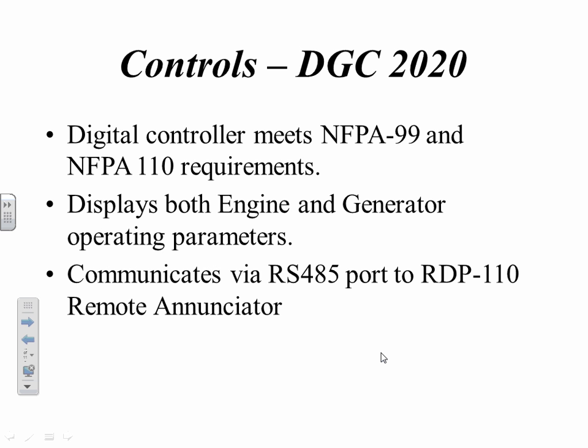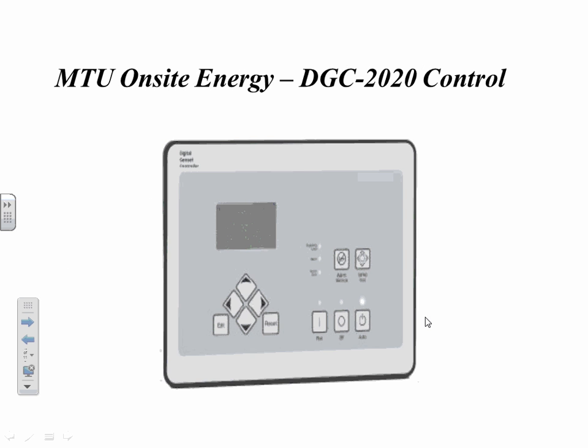Control options that we have. NFPA 110 is probably a regulation you may or may not have heard of, and that applies to generator sets. It displays both the engine and generator operating parameters, AC voltages, kilowatts. We can do that by leg as well, and also all of the engine controls. So we can see oil pressure, water temperature, those kinds of things. We can communicate via an RS-485 port to our remote annunciator. Here's what the control looks like.